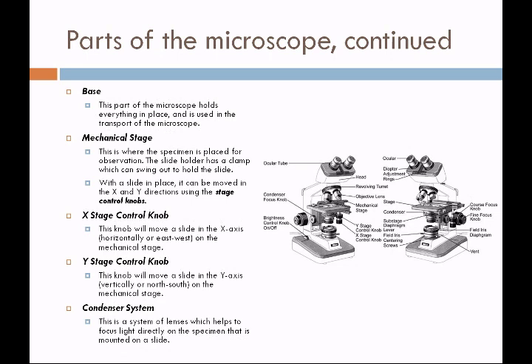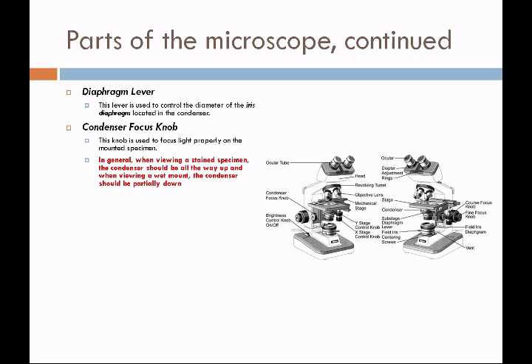Below the stage is the condenser system, which looks sort of like a camera lens. It's a system of lenses which helps focus light directly on the specimen mounted on the slide. The condenser can be moved up and down with the condenser focus knob. The diaphragm lever is found on the condenser and is used to control the diameter of the iris diaphragm. There is a general rule of thumb: when viewing a stained specimen, the condenser should be all the way up, and when viewing a wet mount, the condenser should be partially down.